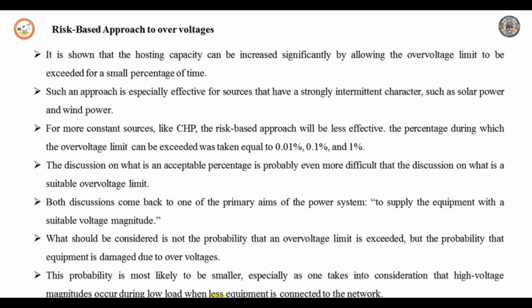To supply the equipment with suitable voltage magnitude, the risk-based approach which has been discussed previously is in fact not fully complete. What should be considered is not the probability that an over voltage limit is exceeded, but the probability that equipment is damaged due to over voltage. This probability is most likely to be smaller, especially as one takes into consideration that high voltage magnitudes occur during low load, when fewer equipments are connected to the network.